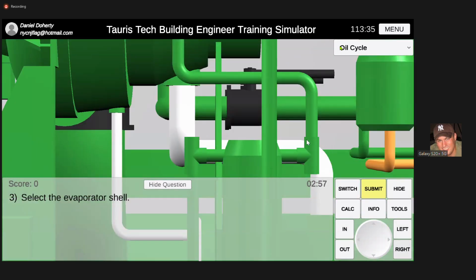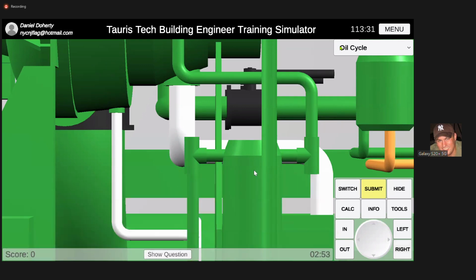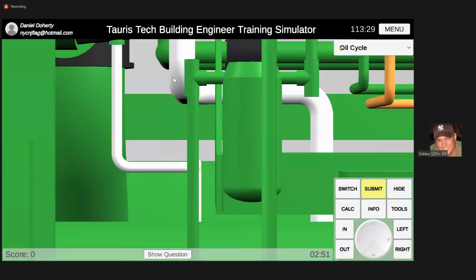You see how they come out a little bit? It's like a T. Yeah. Okay, so if you wanted to isolate this filter, we don't call them open and closing valves. A valve is either front-seated or back-seated. So if you wanted to isolate this filter right here, you would front-seat this valve, which means the valve would go down, and you would front-seat this valve, which means this valve would go this way, and it would isolate this line and this line.